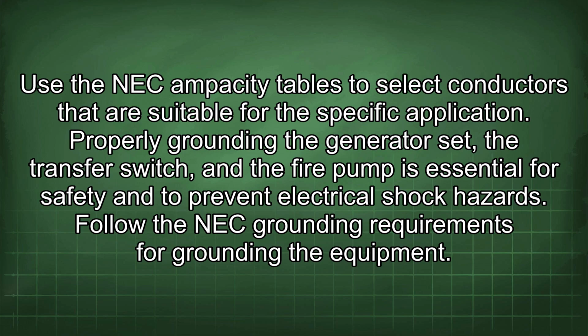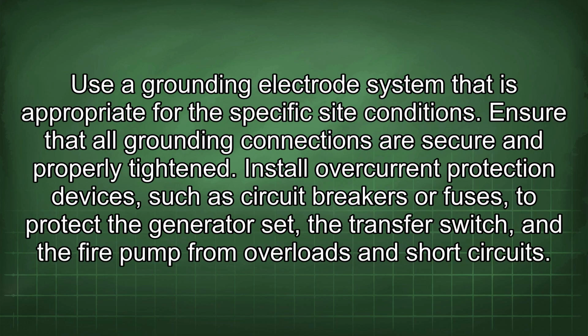Properly grounding the generator set, the transfer switch, and the fire pump is essential for safety and to prevent electrical shock hazards. Follow the NEC grounding requirements for grounding the equipment. Use a grounding electrode system that is appropriate for the specific site conditions. Ensure that all grounding connections are secure and properly tightened.